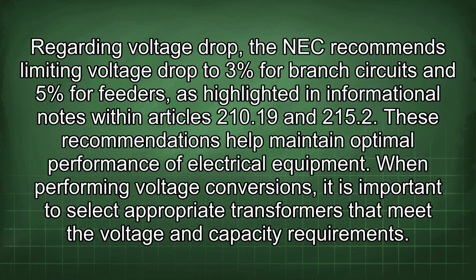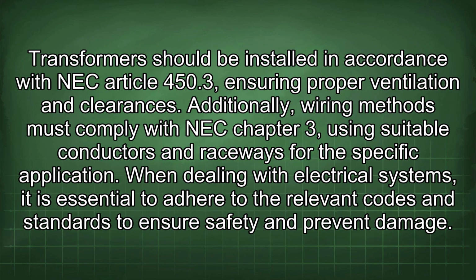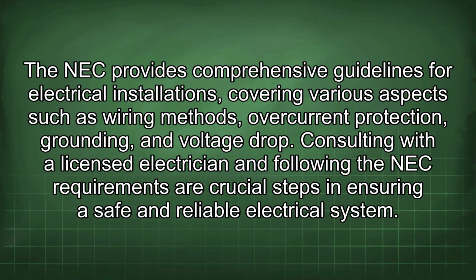When performing voltage conversions, it is important to select appropriate transformers that meet the voltage and capacity requirements. Transformers should be installed in accordance with NEC Article 450.3, ensuring proper ventilation and clearances. Additionally, wiring methods must comply with NEC Chapter 3, using suitable conductors and raceways for the specific application. When dealing with electrical systems, it is essential to adhere to the relevant codes and standards to ensure safety and prevent damage. The NEC provides comprehensive guidelines for electrical installations, covering various aspects such as wiring methods, overcurrent protection, grounding, and voltage drop. Consulting with a licensed electrician and following the NEC requirements are crucial steps in ensuring a safe and reliable electrical system.